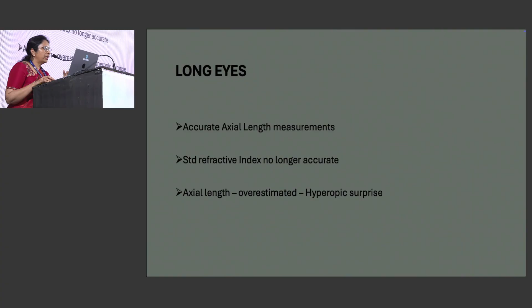Long eyes may also be associated with posterior staphyloma. This is uncommon in eyes with less than 26 millimeters of axial length, but around 60 to 70% of eyes with more than 33.5 millimeter axial length will have a posterior staphyloma. If they have posterior staphyloma, there will be difficulty in obtaining distinct retinal spikes in A-scan ultrasonography. Sometimes the A-scan will measure the anatomical axial length, from the corneal vertex to the posterior pole, instead of the refractive distance, from the corneal vertex to the center of the fovea, because there is no way to identify the fovea.